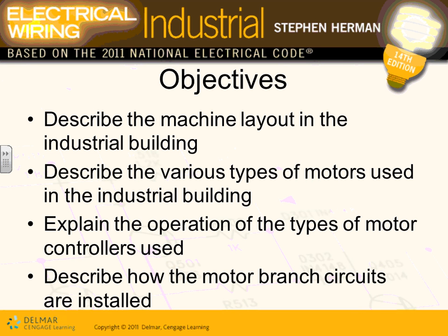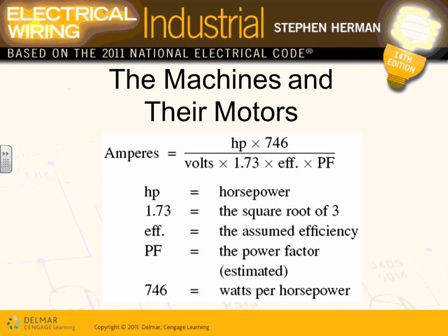We just remind you, because we did branch circuits and feeders for motors. I am confident that all of you will be tested, by the way, on Friday on it. How to do branch circuit calculations on a disconnect, overcurrent protection device, fuses, overload, all this, as well as the feeder. So I'm confident that we covered these really well.